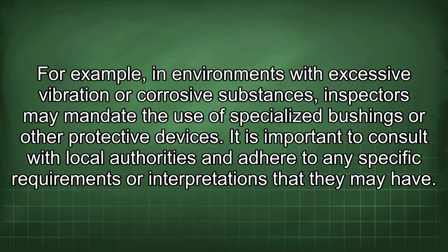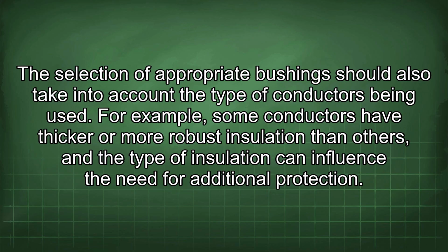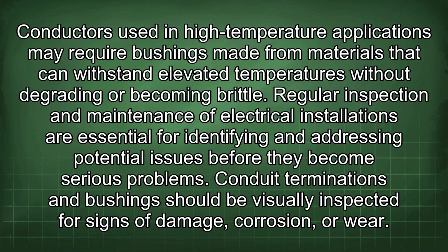The selection of appropriate bushings should also take into account the type of conductors being used. For example, some conductors have thicker or more robust insulation than others, and the type of insulation can influence the need for additional protection. Conductors used in high-temperature applications may require bushings made from materials that can withstand elevated temperatures without degrading or becoming brittle.